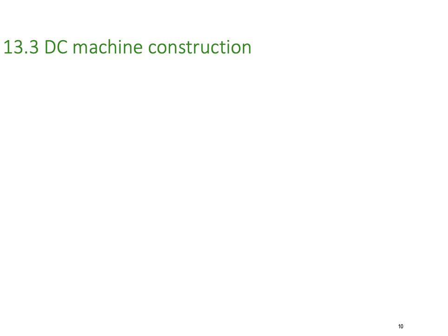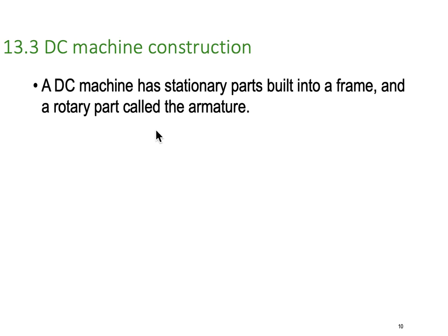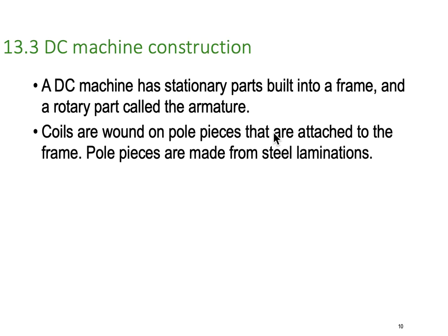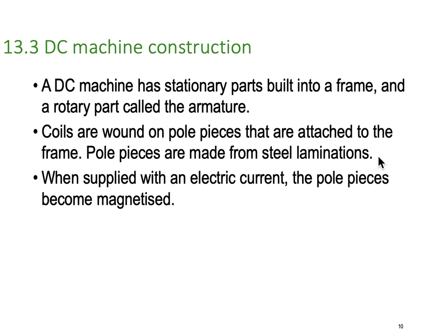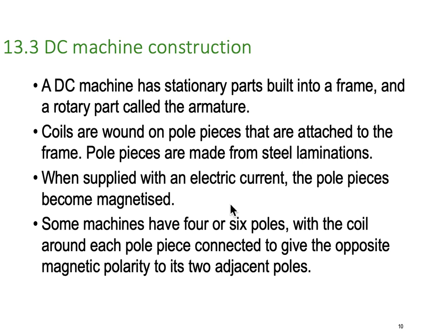A DC machine has stationary parts built into the frame or stator, and rotary parts called the armature. Coils are wound on pole pieces attached to the frame, which are made from steel laminations. When supplied with electric current, the pole pieces become magnetized electromagnets. Some machines have four or six poles, with the coil around each pole piece connected to give the opposite magnetic polarity to adjacent poles.